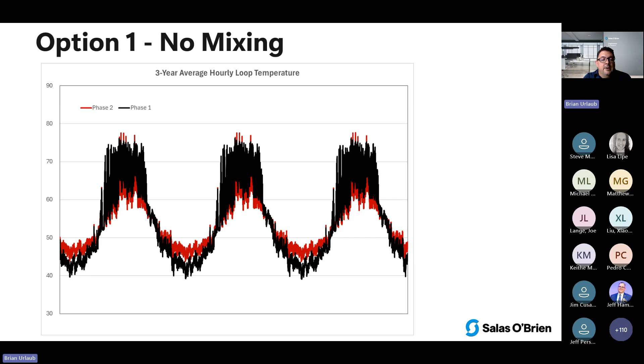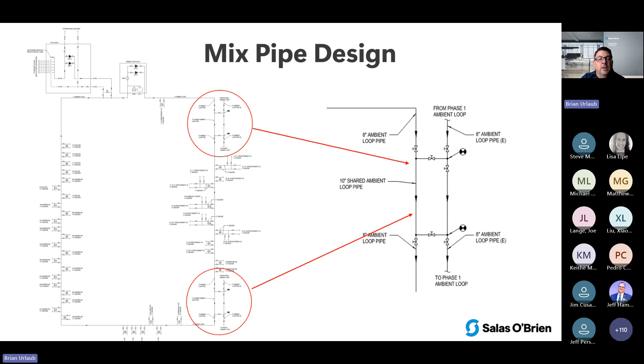So what we came up with is a 20-foot section of pipe being replaced rather than the entire length of that north and south street. If we do it in both locations, top and bottom, we don't impact the hydraulics and pumping because we can upsize that to a 10-inch pipe. We can flow both flow rates through that 10-inch section without increasing the head pressure on the first phase pumps, and still get enough thermal sharing in those two 20-foot sections to make a difference. That's what we came up with running through TRNSYS and our hydraulic pipe flow models to do this cost effectively.